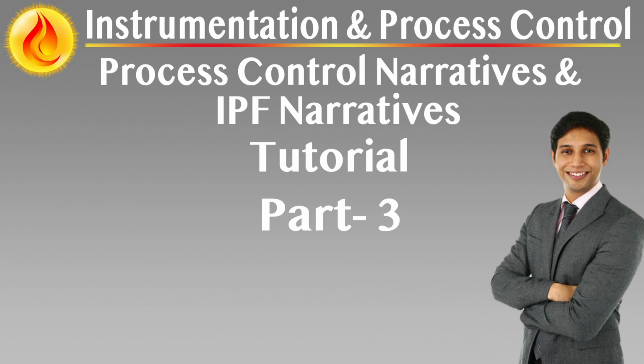IPF applicability across operating modes. Not all IPFs are required or active in every operational mode. It must be specified whether the IPF is applicable during startup, normal operation, shutdown, foreseeable abnormal conditions, e.g. loss of utility, flare system limits. Mode-specific IPFs must be clearly identified. For example, certain protections may only be required during startup while others are continuously armed. This information supports proper system arming and interlock logic.